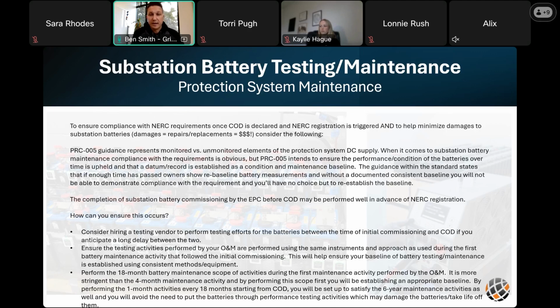Once the timer starts, you have an obligation for a portion of PRC5 to have your batteries maintained within the first 4 months of COD or NERC registration. That's the compliance requirement for PRC5. But from a practical standpoint, you haven't really maintained the batteries by the time the O&M performs the initial maintenance activity a month after the site is operational—it could be 16 or more months in that scenario.